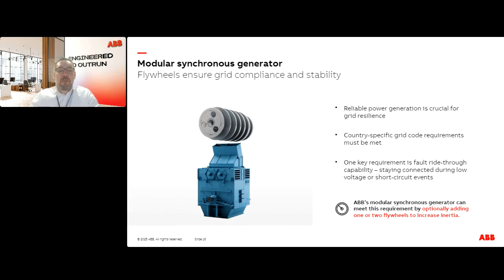So we have the option to add inertia on top of the rotor itself, one flywheel on the drive end of the generator and one flywheel on the non-drive end of the generator. So then the maximum inertia of this machine is something like 33,000 kg·m². So basically, with this solution, we can comply with basically any grid code requirement of today and tomorrow as well.